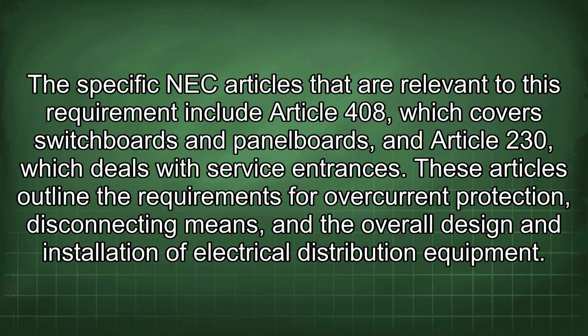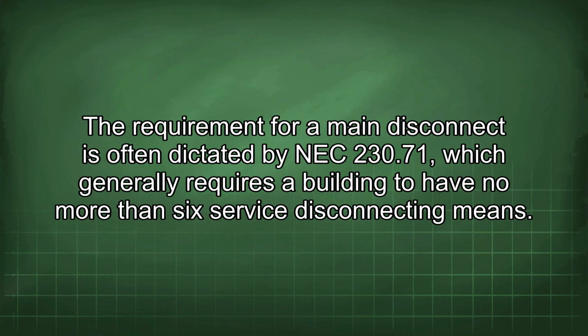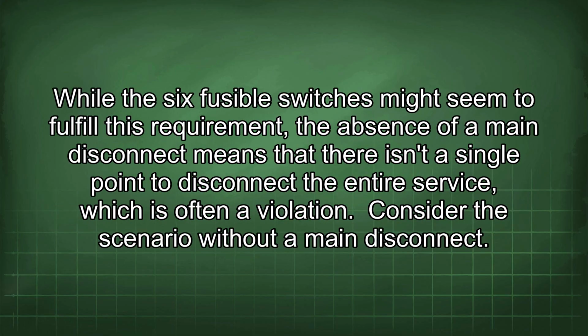The specific NEC articles that are relevant to this requirement include Article 408, which covers switchboards and panelboards, and Article 230, which deals with service entrances. These articles outline the requirements for overcurrent protection, disconnecting means, and the overall design and installation of electrical distribution equipment. The requirement for a main disconnect is often dictated by NEC 230.71, which generally requires a building to have no more than 6 service disconnecting means. While the 6 fusible switches might seem to fulfill this requirement, the absence of a main disconnect means that there isn't a single point to disconnect the entire service, which is often a violation.